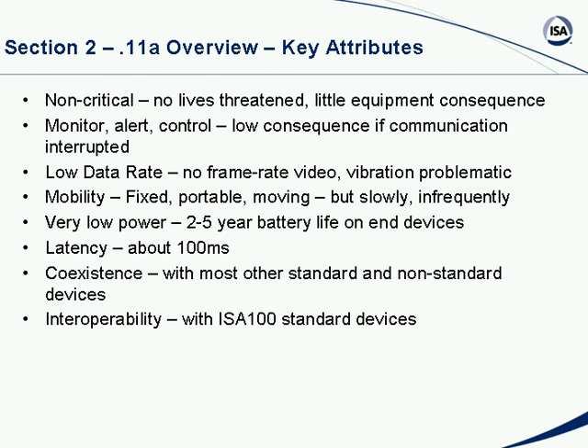Little equipment consequence is in the eye of the beholder — so when a prospective application comes along, somebody has to say this is a sufficiently low consequence that I can use a non-critical designed wireless standard for it. It's primarily for monitoring, alerting, and low-level control — again meaning low consequence if communication is interrupted. You don't want a life-threatening control system based on this standard. It will be low data rate — you sure don't want to run frame-rate video over it. You can run vibration sensors: if you sample infrequently, sending the signature once a day, it would have little impact. But a vibration sensor dumping a signature every minute could quickly swamp the anticipated data rate.